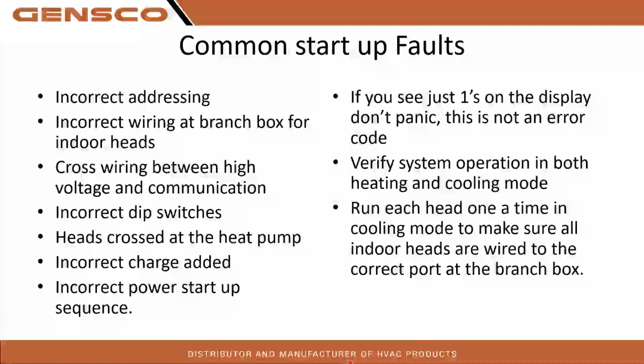So one of the things when you guys are doing your startups on this, what you should be doing is testing your system in both heating and cooling. There are options to test run those things either through your thermostat or maintenance tool if you have your maintenance tool hooked up. But I highly recommend that all of your systems, whether it's Smart Multi or MXZ ported units, you test each head individually in cooling.